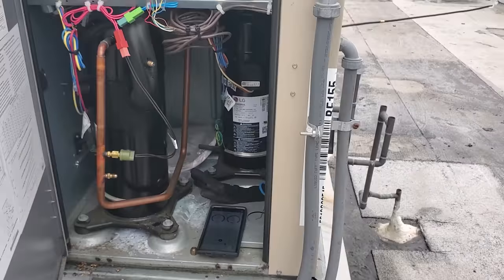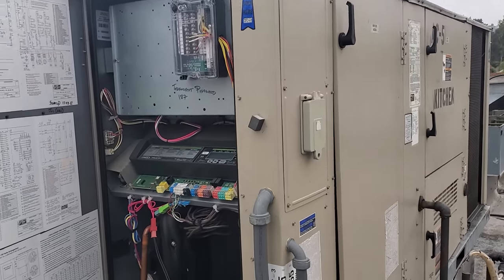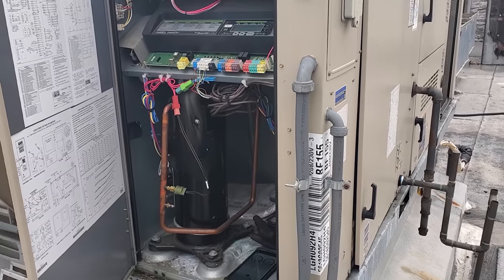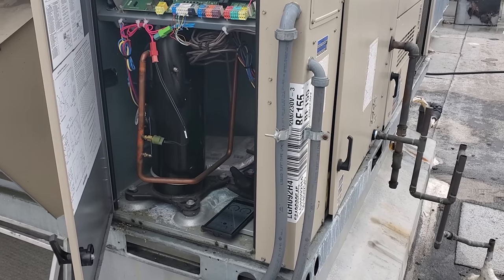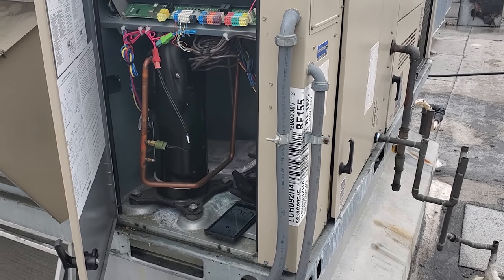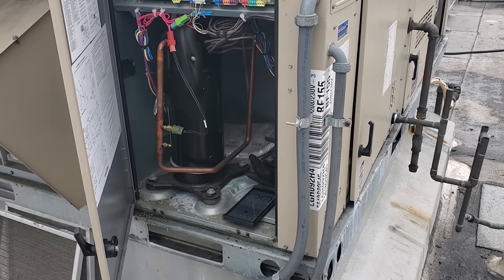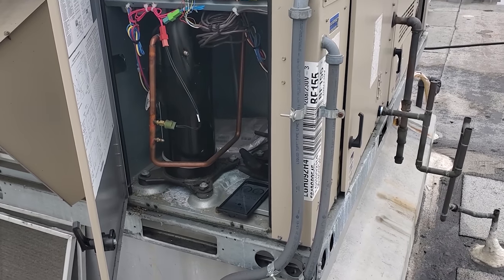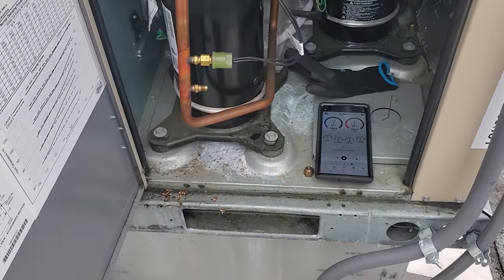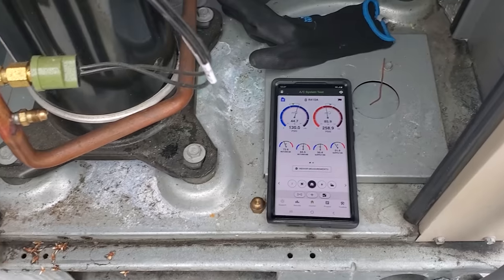This really makes you realize you can't just come to the air conditioner and assume you're going to solve your problem. They're complaining about condensation dripping from the vents, but it's not just a simple fix. They've got so many things going on: every vent in the kitchen is uninsulated on top, the hood filters are plugged up, the dishwasher isn't trapping steam, the damper was open. You can't just look at the first issue and assume - you've got to look at the big picture. Big picture diagnoses.